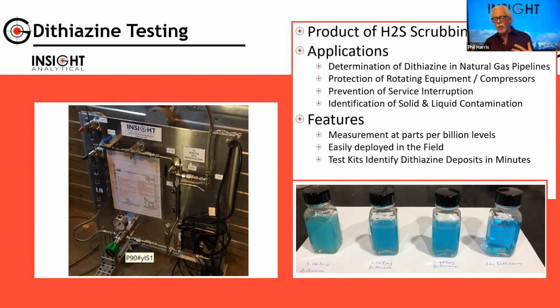So it's become important to find a way to measure this dithiazine. The difficulty is it's often there at parts per billion type levels, so we need very sensitive technologies to detect it, especially in the gas phase. So Insight has developed a methodology in conjunction with Alberta Sulfur Research to use a trap type method. We can put this panel out in the field. It has a column over here that's a trap. It absorbs dithiazine over a period of time as natural gas flows through it.